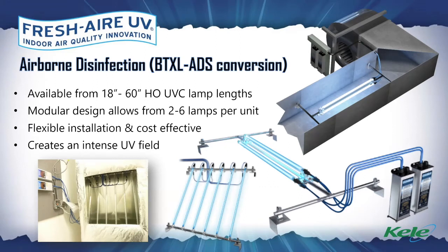The ADS can be mounted in both a parallel orientation, which you see there, and in some instances, we do use what we call grid style. As you see there, it's mounted on a 45 degree angle, again, to extend the parallel orientation to airflow, but it covers more ductwork on a single pass. But the most common application for these types of systems is definitely the axial type, we call it, which is the parallel torpedo type format mounted in the center of the ductwork.